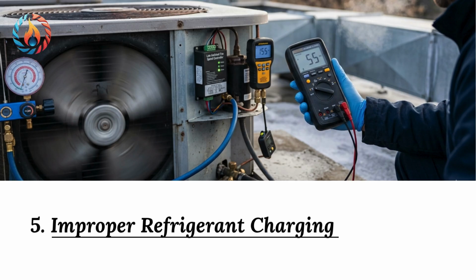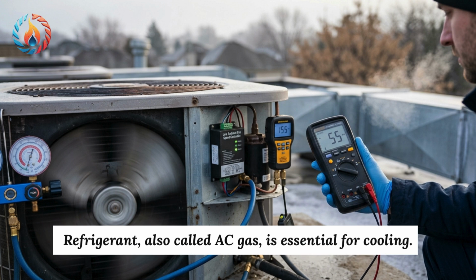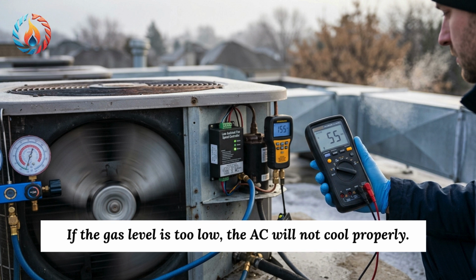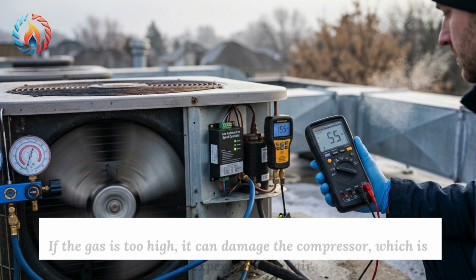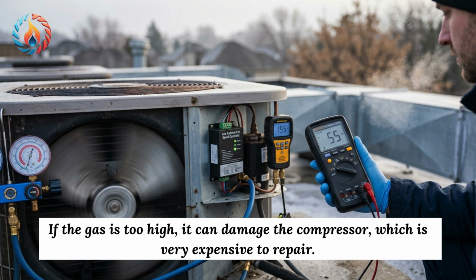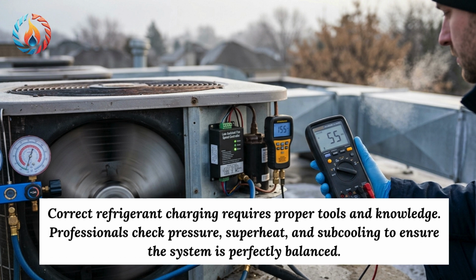5. Improper refrigerant charging. Refrigerant, also called AC gas, is essential for cooling. If the gas level is too low, the AC will not cool properly. If the gas is too high, it can damage the compressor, which is very expensive to repair. Correct refrigerant charging requires proper tools and knowledge. Professionals check pressure, superheat, and subcooling to ensure the system is perfectly balanced.